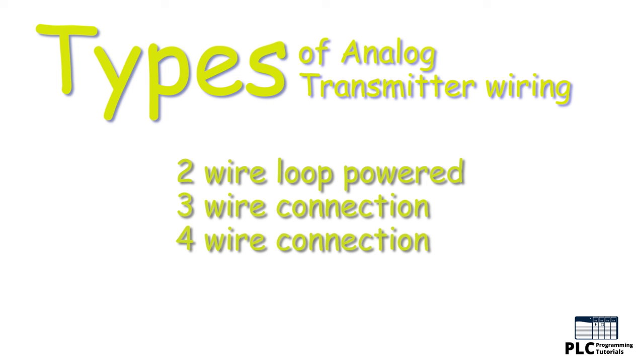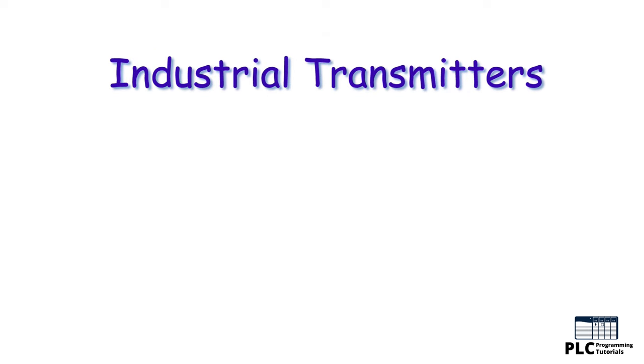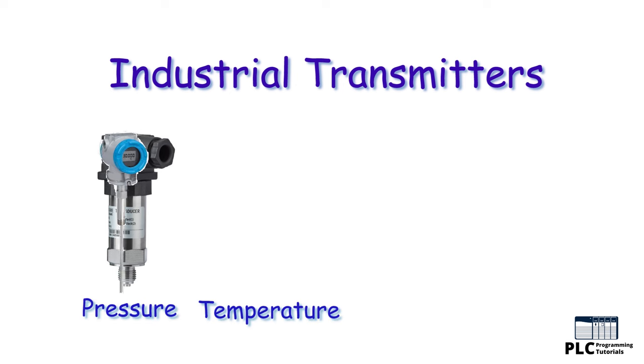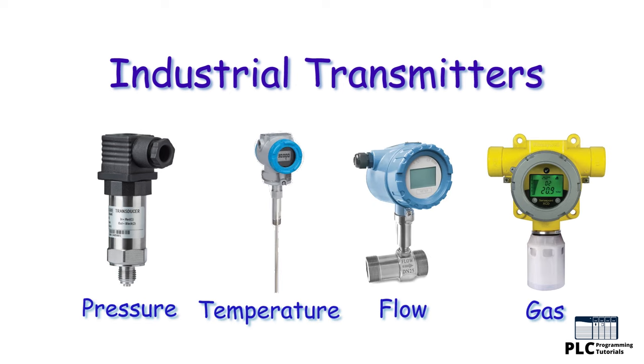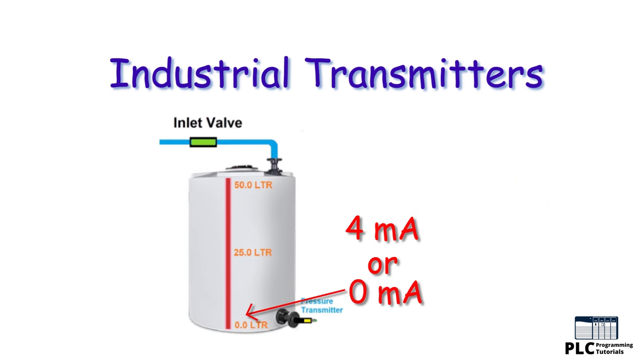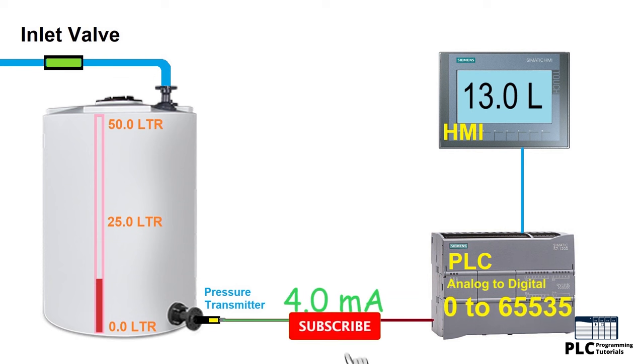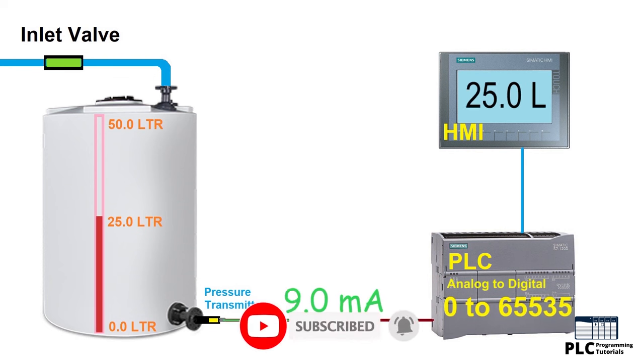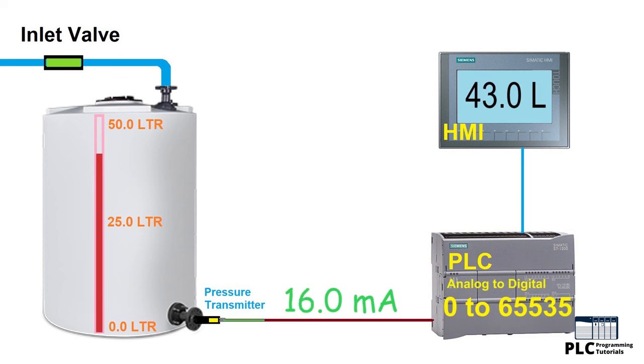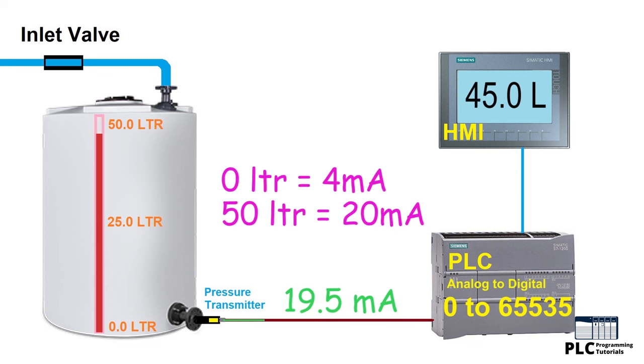Industrial transmitters are available for monitoring many parameters. These include pressure, temperature, flow, and gas detectors. Transmitters offer 4 to 20 milliamp outputs where 4 milliamps equates to a zero reading and 20 milliamps equates to a full-scale reading of the calibrated range. This signal is sent to a remotely located control panel, which uses this signal to perform actions via relay contacts or show alarms on the HMI screens.